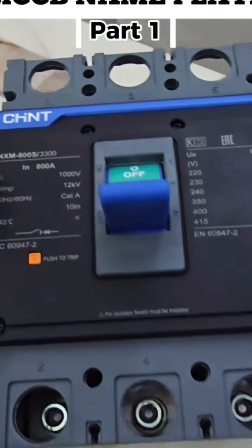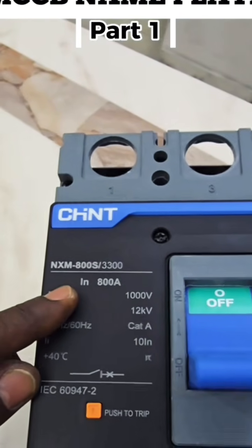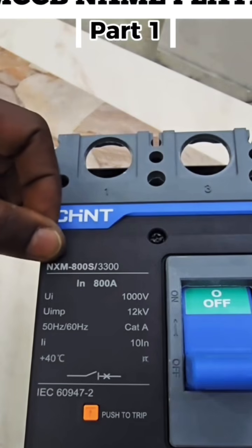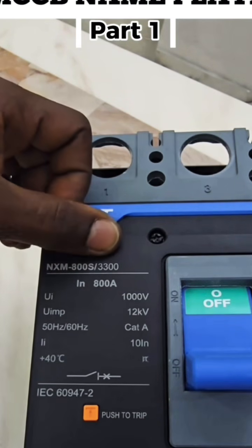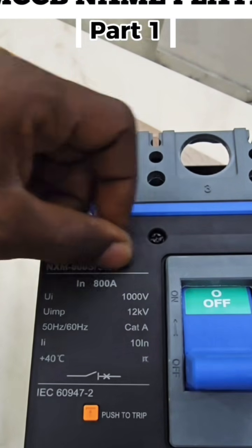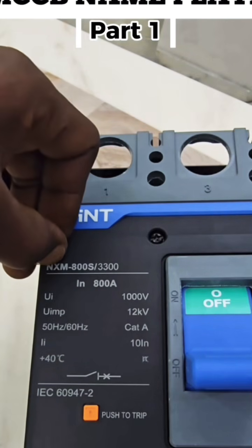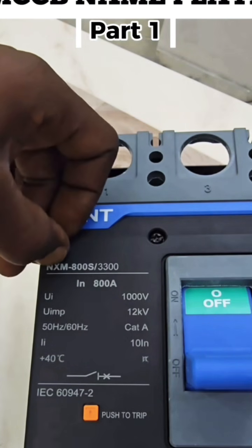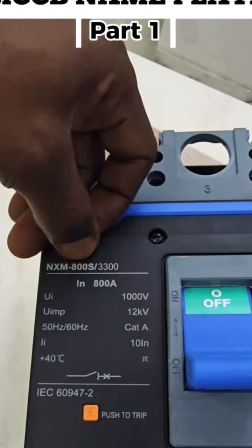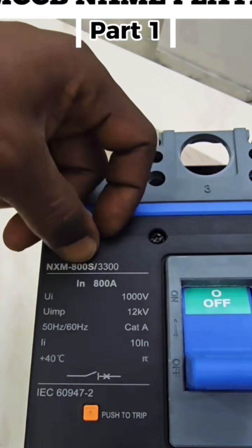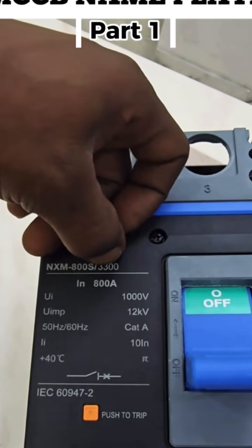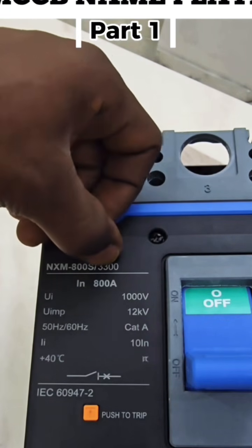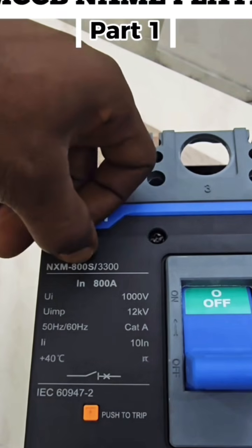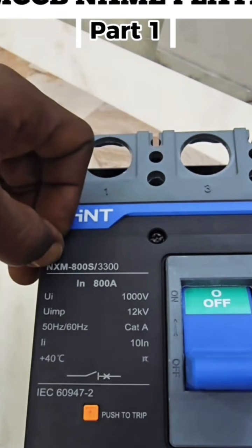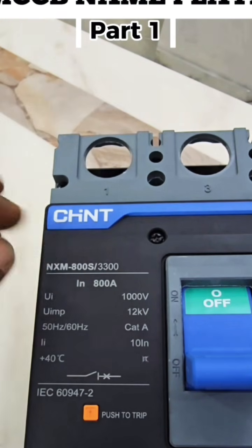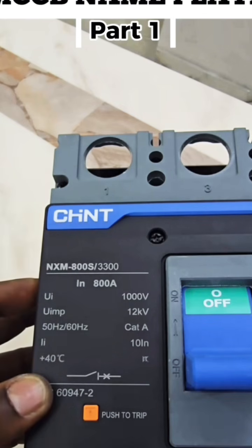First, we're going to start with the name of the circuit breaker, NXM-800S/3300. This stands for, number one, the frame size of this circuit breaker; this one stands for the breaking capacity, while this one is the pole number. This is a 3-pole circuit breaker with a capacity of 800 amps, and the frame size is determined by the manufacturer.